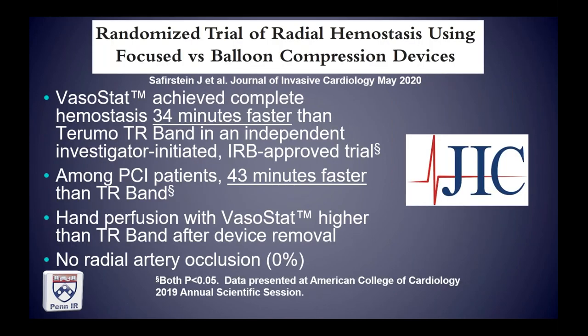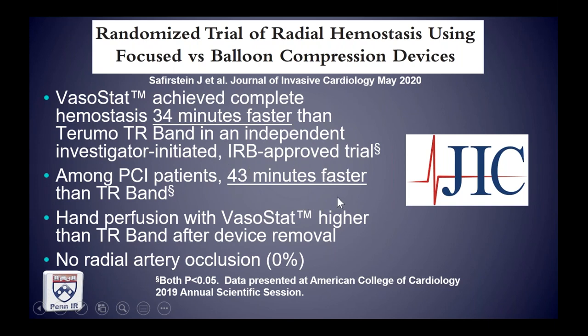During development, randomized trials were done. Compared to the market leader, the VasoStat achieved complete hemostasis 34 minutes faster than the Terumo device — in both diagnostic and interventional patients — and among patients undergoing cardiac catheterization with intervention, nearly three-quarters of an hour faster than the TR band.